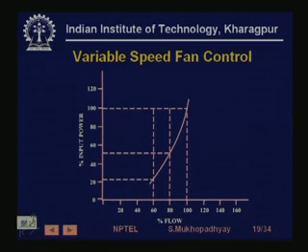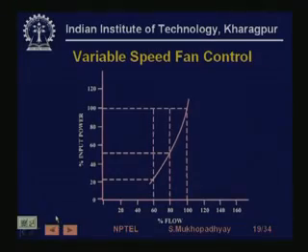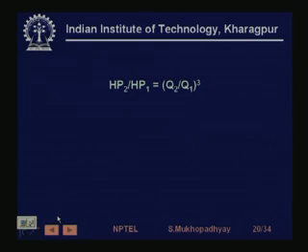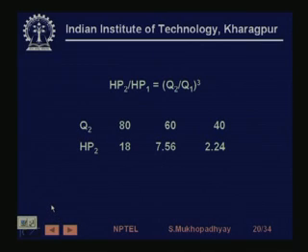So, this is the essence of energy. This shows how energy saving a variable speed drive can be. Just to drive the point home, we are just applying that same formula. Remember that at Q1 equal to 100, we had a HP requirement of 35 HP.